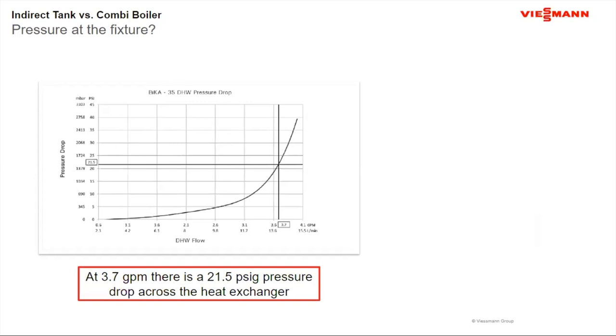Second person jumps in, they start to take a shower. Now all of a sudden my flow rate goes from 1.8 gallons per minute up to about 3.7. My pressure drop goes from about 3 psi up to about 21.5 psi. The person in that first shower all of a sudden sees the amount of water coming out of the showerhead start to reduce. So when I look at combi boilers and high flow rates, a lot of times they are associated with a high pressure drop. So it is something you have to consider.